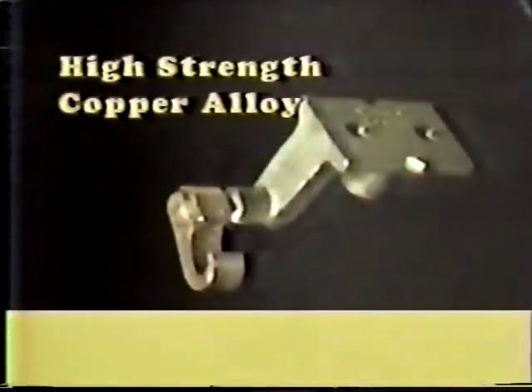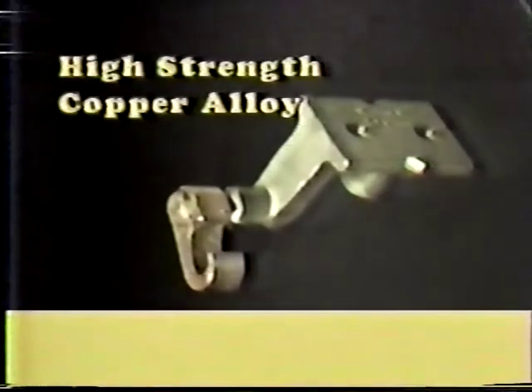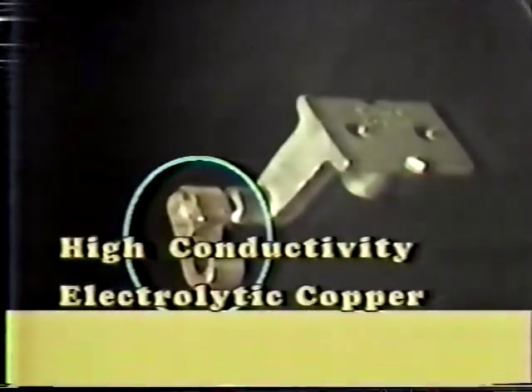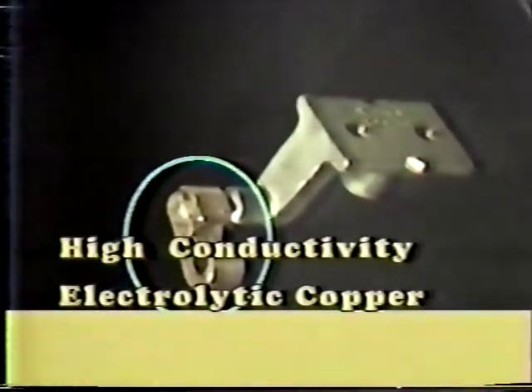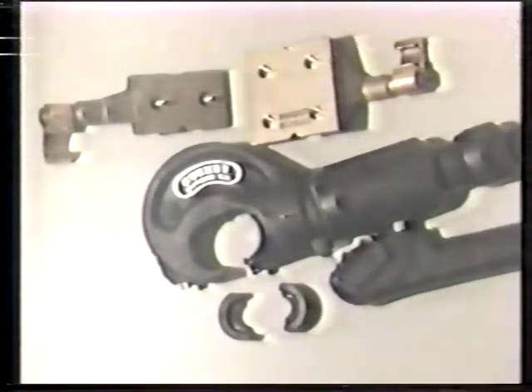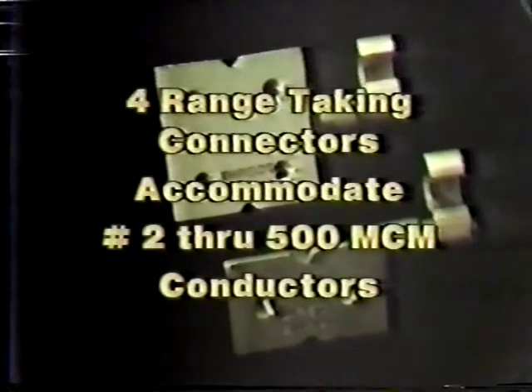To ensure durable threads, Burndy's grounding plates are made of a high-strength copper alloy, and the compression connector is made of high-conductivity electrolytic copper. Burndy's ground plates can be installed with the same tools and dies as the rest of the Hyground line. Burndy's ground plates are range-taking.